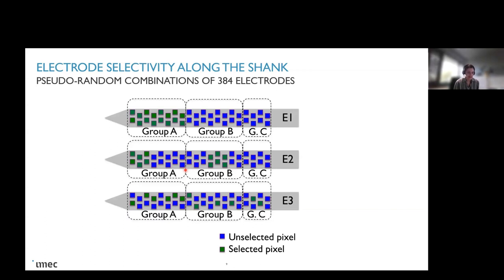Another thing that is very special in Neuropixels probes is that we have many more electrodes than channels that we can record simultaneously. So what it was important is to try to create a way to select those electrodes in a rather flexible way, so that you can choose which electrodes are the best to be recorded in a single experiment. And for this, then we enable certain selectivity options. For example, you are able to select groups of 384 electrodes that are all consecutive, or you can spread those electrodes in different regions along the shank. And there are of course, some options that you cannot select. But the idea is to be as flexible as possible within the limitations of the wiring. That was the goal, also for Neuropixels one. And this also applies to Neuropixels two.